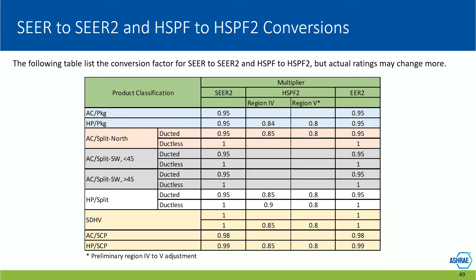So I put this chart in, and you can't find this in 90.1. This is your handy dandy converter chart showing what SEER 2 is relative to SEER. For an air-cooled package unit, SEER 2 decreased the efficiency by 5%. But when you look at the new efficiencies, they're actually higher because at the same time we made the change from SEER to SEER 2, we increased the efficiency. So we went to a 15 SEER level, but that's actually a 14.3 when you do the derate for the static. I thought that might be useful since not everybody has all the new numbers out there for you to use. Next slide, please.